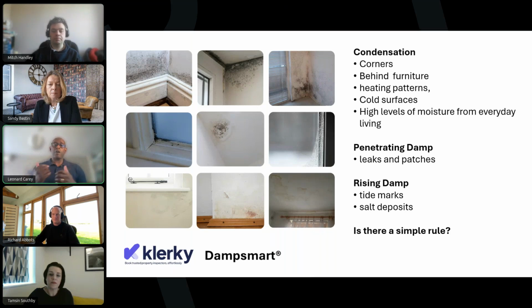So they were opening windows, and we could see that in the data, but they weren't getting the benefit of drier air outside because it wasn't drier air. Suddenly the conversation turned from, all right, you're not doing the best you can possibly do, to, okay, so how are we going to extract that moisture from that property? And that's a completely different conversation than saying it's the way that person was living.